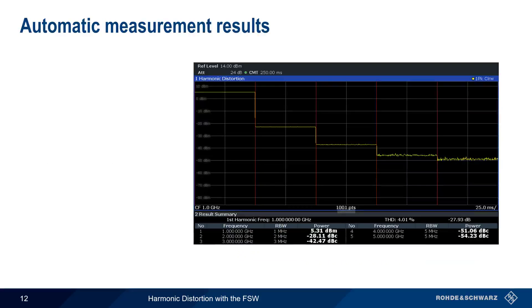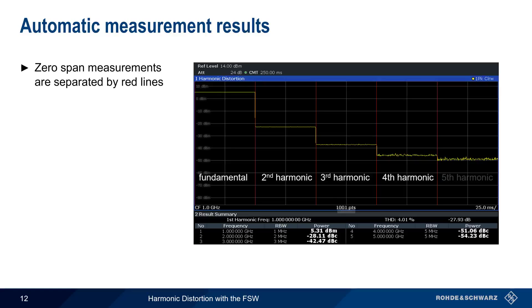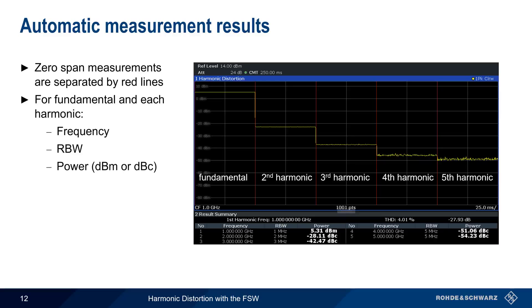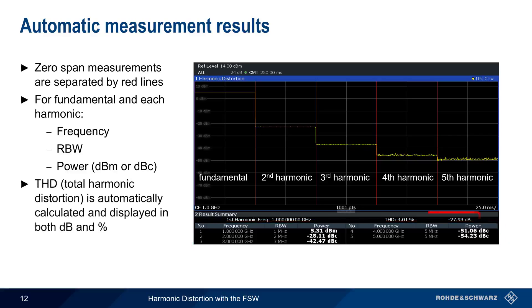In the measurement results, each zero-span is separated by red vertical lines. In this screenshot, we see values for the fundamental, second, third, fourth, and fifth harmonics. For the fundamental and each harmonic, the values for frequency, resolution bandwidth, and measured power are provided in a table. In addition, total harmonic distortion (THD) is automatically calculated for the measured harmonics and is given both as a percentage and in dB.